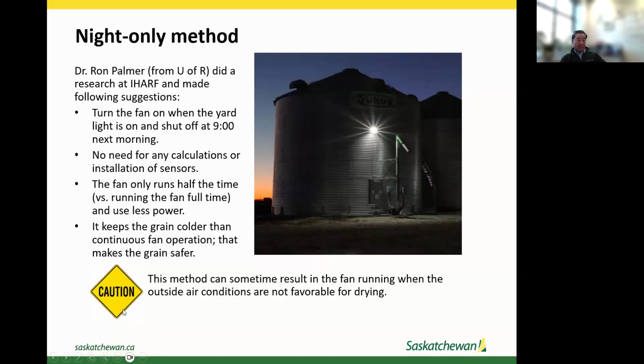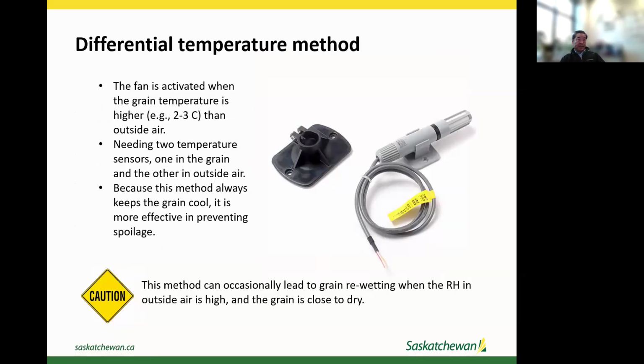That's what he's suggesting. The method itself is not perfect because sometimes it will result in the fan running when the outside air conditions are not favorable for drying, particularly, let's say, on a rainy night when the air is warm and the air moisture is really, really high.